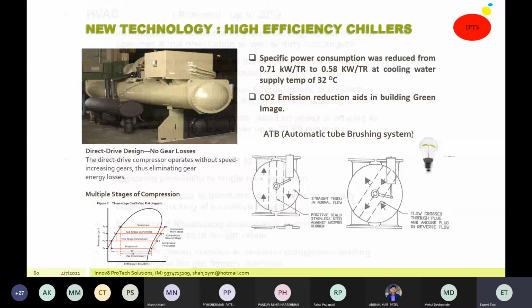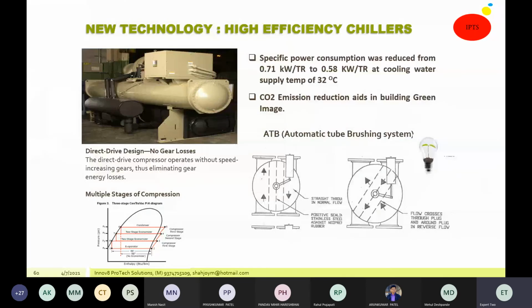One good technology available is self-cleaning exchangers. It's not a new one. It was practiced 10 years back also, but it was not very popular. In recent times, it is getting popular so that your cooling water exchanger doesn't get fouled. It uses balls for self-cleaning, or an automatic tube brushing system, so that the efficiency of the chiller or cooler is not reduced. So by all these things, perhaps ultimately you are targeting to reduce electrical energy consumption.